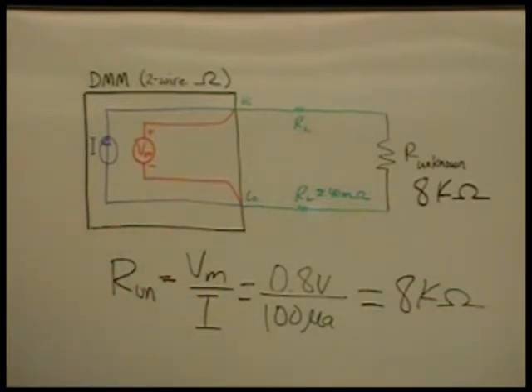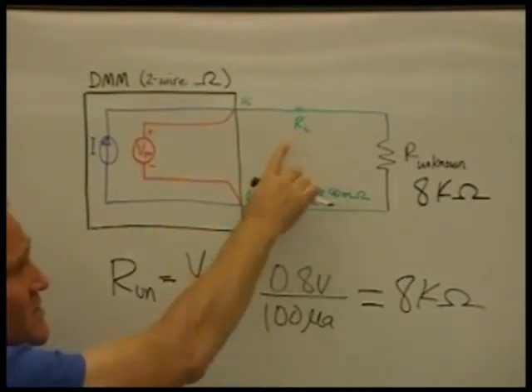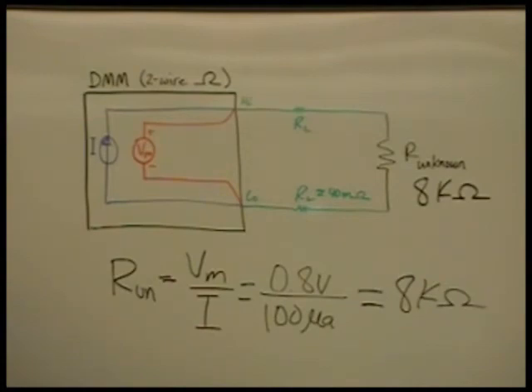So again, this video is just designed to give you an overview of how resistance measurements are made. And the main thing you need to remember about a two-wire-ohm measurement is that the lead resistance must be negligible compared to the unknown resistance you are measuring.